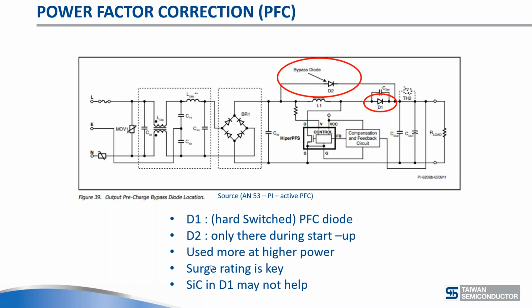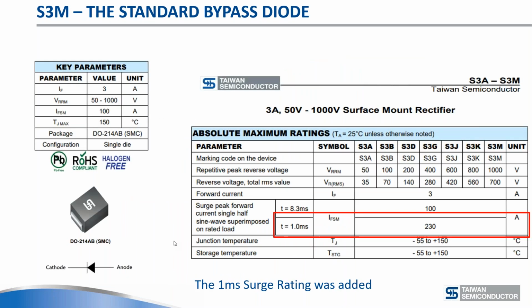That's why the most common one used in this application is the S3M device in a SMC package. Because it's used just in the startup phase, we add the 1 millisecond time rating for surge. Why is that important? Most of the time, when you charge a capacitor, you're somewhere in the area of a couple hundred microseconds, 200 to 300 microseconds. So if you have your surge rating at 1 millisecond, you can be pretty sure by adding this to the data sheet. You don't have to think about whether a 100 amp surge rating is okay for a 200 amp surge. You can look and see it passes 230 amps at 1 millisecond, so you'll be okay in your application. This is just an added security we built in for the designer.